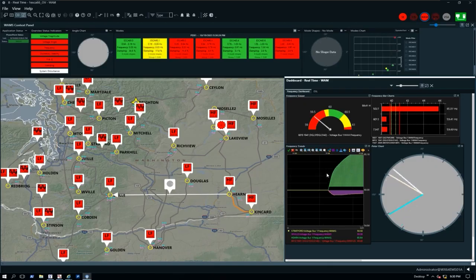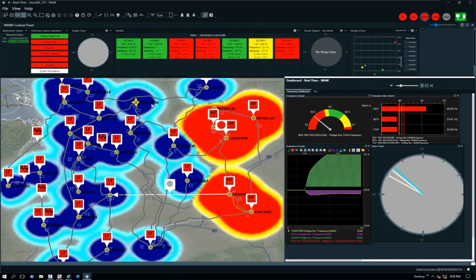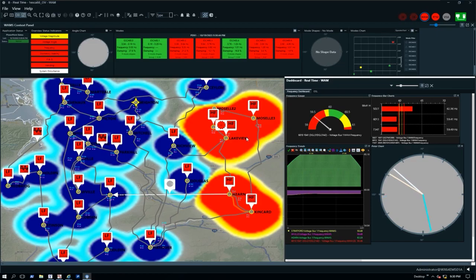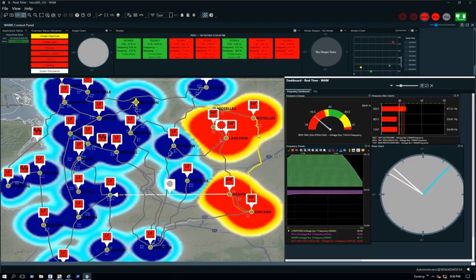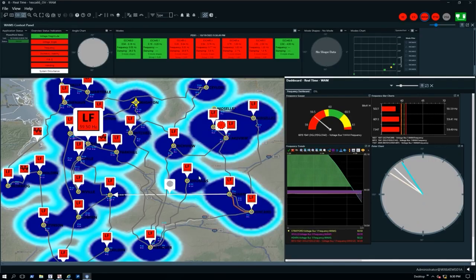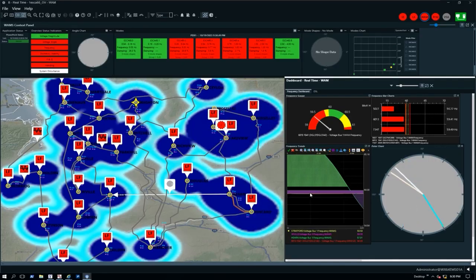You can see that our two islands have separated. Let me turn on my frequency halos, which help visualize the differences in frequency. So the smaller island is the curve that's shooting up. We're getting a very high frequency because we've got a lot of generation and little load in this island. And then we've lost that generation source to the bigger island, so our frequency has declined from nominal.